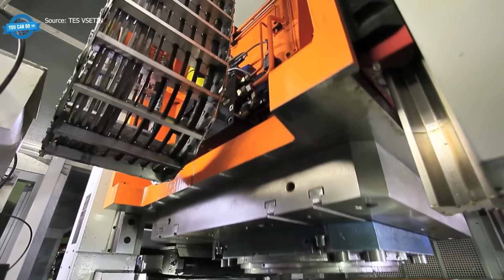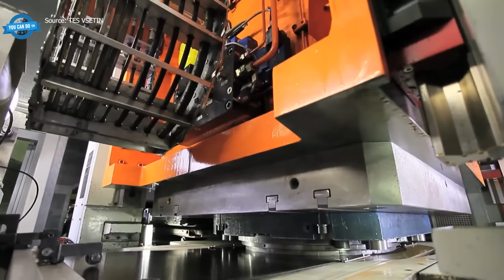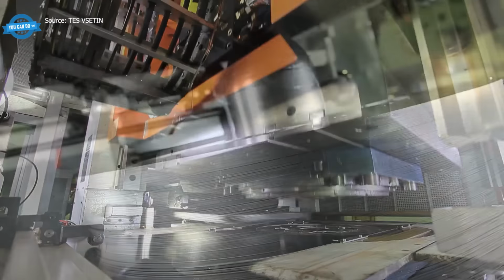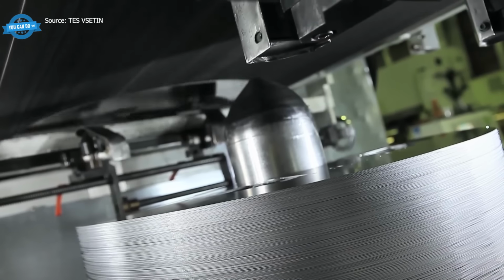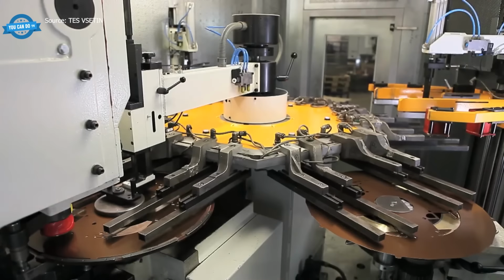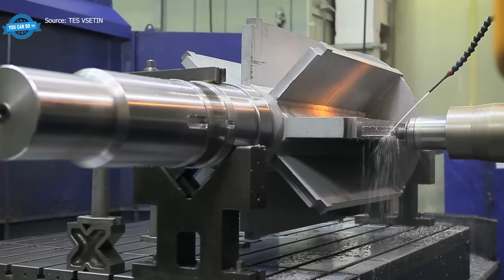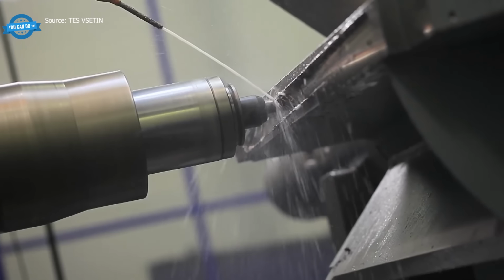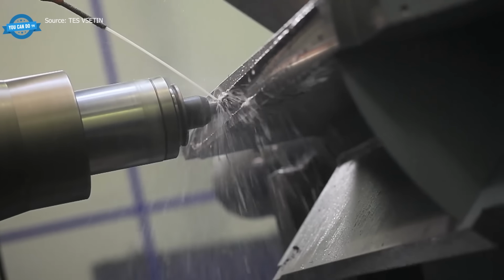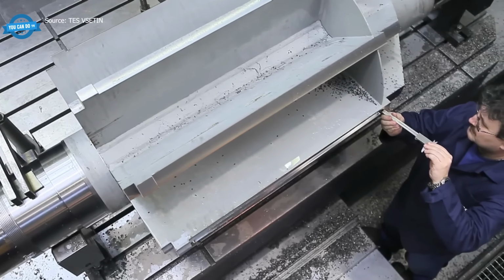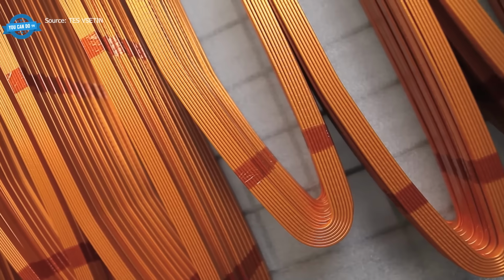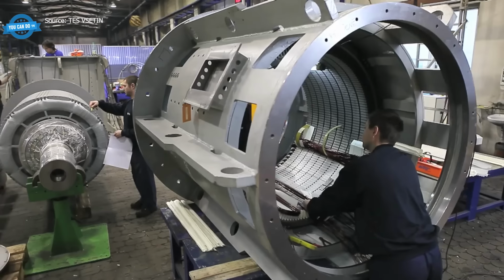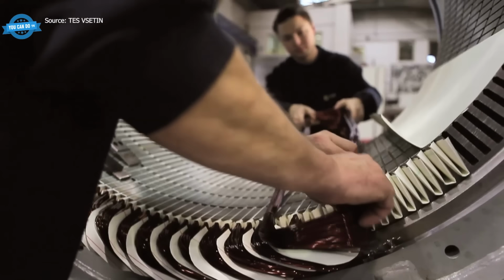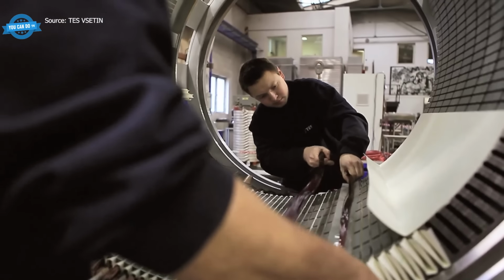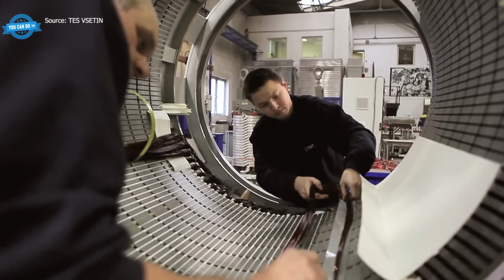The diesel engine generates torque, but in many mining machines, that torque is converted to electricity before it reaches the wheels or the cutting system, and the quality of that conversion depends on what happens inside the generator. Large industrial generators and motors are built from silicon steel laminations stamped to a precise profile and stacked under hydraulic pressure to form the stator core. Stacking reduces eddy current losses that would otherwise convert electrical energy into waste heat at the core. Copper conductors are shaped into coils and wound into the stator slots by hand, with each slot lined with insulation material before the first conductor is placed.